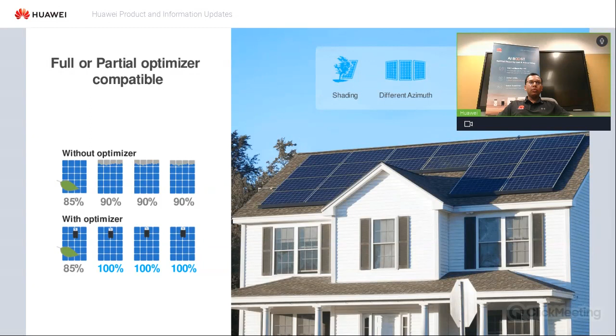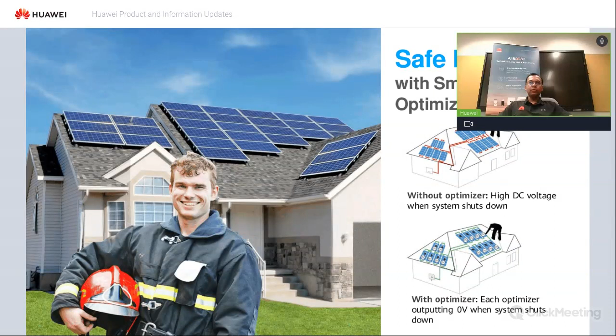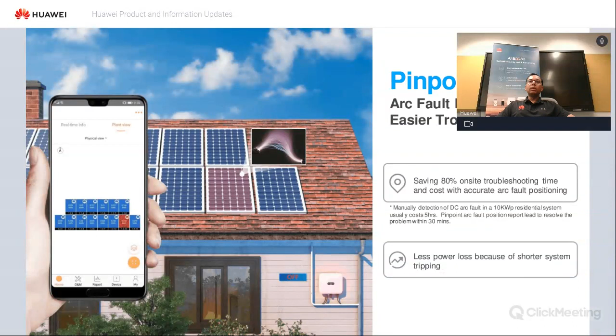Another point, however, if you do have full optimizer solution, there's two distinct advantages. One of them is that whenever the system shuts down, the output is down to 0 volts, making the roofs a lot safer for anyone that needs to do any maintenance work up on the roof. And another advantage of full optimizer solution is panel level monitoring. So with the same FusionSolar app that we've been talking about before, if there's full optimizers installed, you can have panel level monitoring, and for any arc faults or any kind of faults, it shows up on the app. So the installer or the maintenance person can just go directly to that panel rather than troubleshooting every single one. So that's going to save a lot of time.